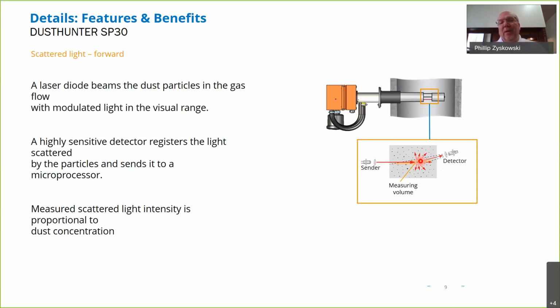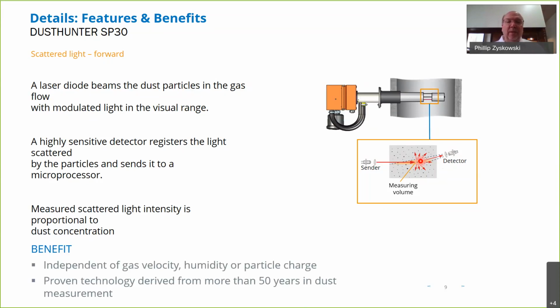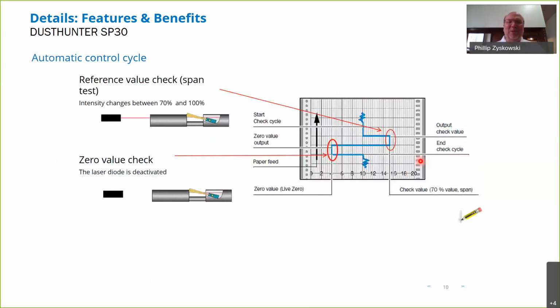And we have different techniques. In some cases, we use back scatter for other applications, but for the Dust Hunter SP30, forward scatter was the best and most robust and gives us that wide detection range of different particles. So the benefit there, it doesn't matter what velocity you have, how varied your humidity or particle charges are of that dust. And again, it's been a proven technology. This isn't a beta type technology. This is something that has been proven over the years in the laboratory and a lot of our other installations.